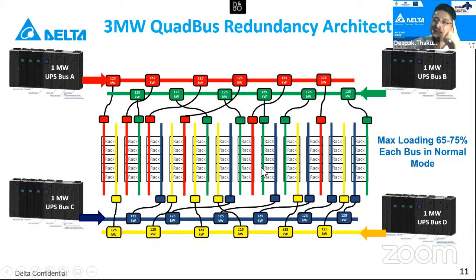Now the point here is the end rack still has the 2N architecture. It's not that these are parallel together as an N plus one bus, which was the traditional way of the tier 3 approach. Out here, I don't know whether it falls in tier 4 or 3, because again, our systems of designs or certifications have to also upgrade themselves to adopt these kind of designs and upgrade them to tiering levels. So currently this design itself can deliver you a 2N architecture to your particular rack with almost the number of UPSs going down. So what is the summary of this?